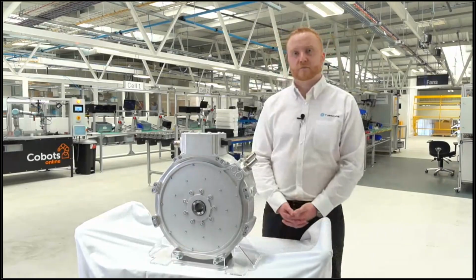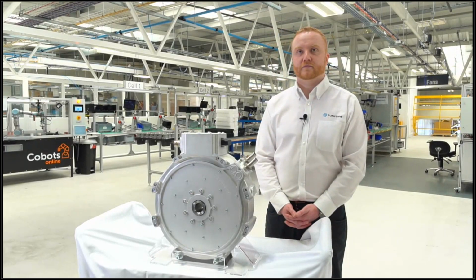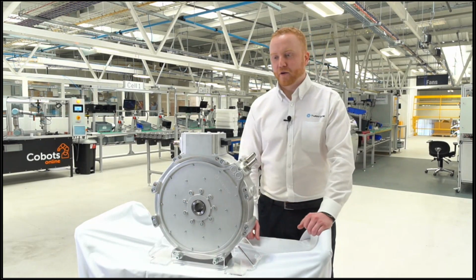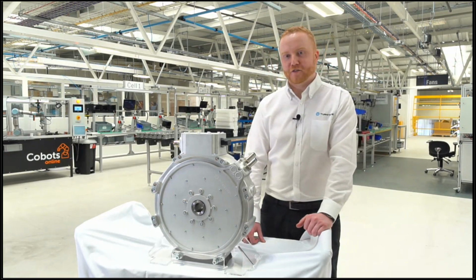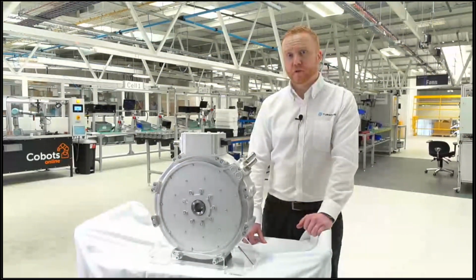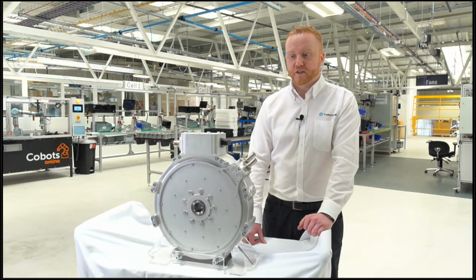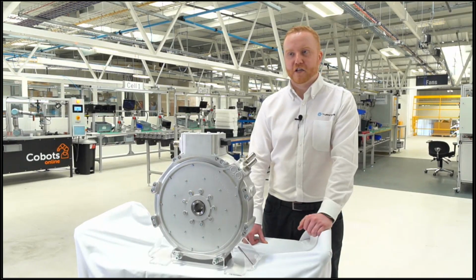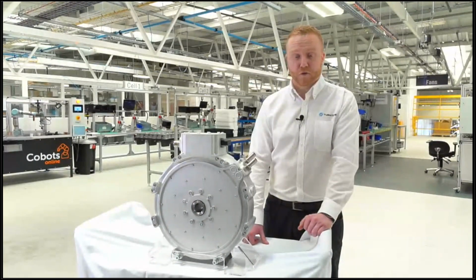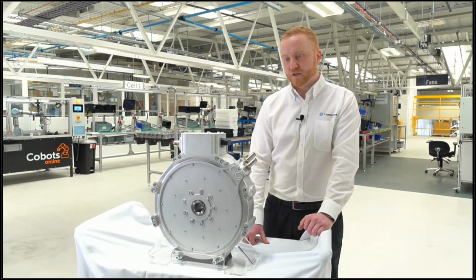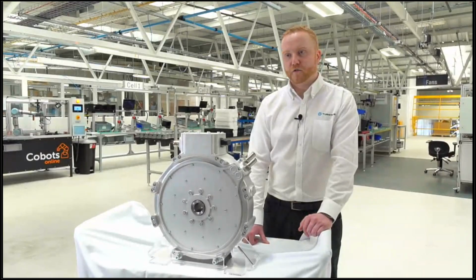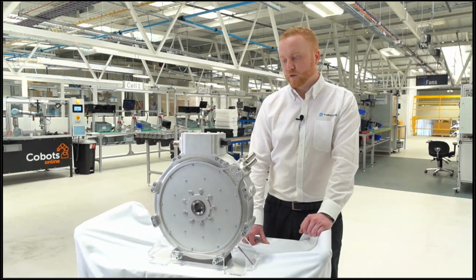Does axial flux motor technology have an effect on the bearing discharge problem for the shaft bearing? Bearing discharge is a topic you could do a multi-hour lecture on alone. From the research we've done, the testing we've done, and engagement with industry experts, we see very low risk. You can never say zero since it requires years of testing, but it's very low risk. We've also integrated an Aegis ring within this design to allow pass-through and reduce buildup of voltage on the rotating assembly.